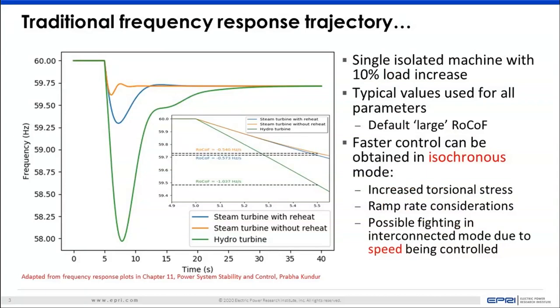And just to give a recap of how this is represented, there's this classic block diagram representation, which is in Prabha Kundur's book, chapter 11, actually. And this plot is adapted from that. If you look at the response, which contrasts a steam turbine which has a reheat feature, a steam turbine which does not have a reheat feature, and a hydro turbine, in a single machine isolated scenario, and if you put a 10% load increase on these types of machines with typical parameters from the book, then you by default seem to get a large RoCoF.